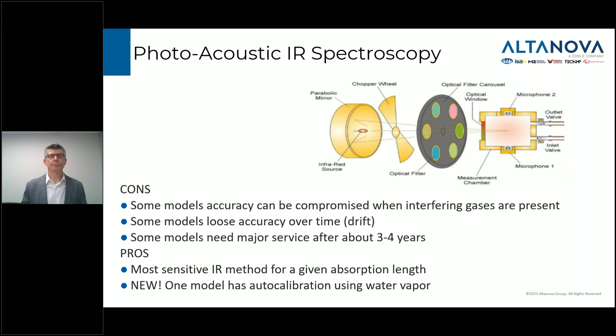There are, of course, also some advantages. It's intrinsically the most sensitive of the techniques, which is important because we're often measuring very small concentrations in our applications. So for detecting small amounts of emerging gas associated with new faults, having that high sensitivity is an advantage. And I'm happy to share with you today there's a new model on the market using photoacoustic techniques that has a built-in automatic calibration system that helps to compensate against the drift that has historically been an issue with this kind of approach. So let me talk about that on the next slide.